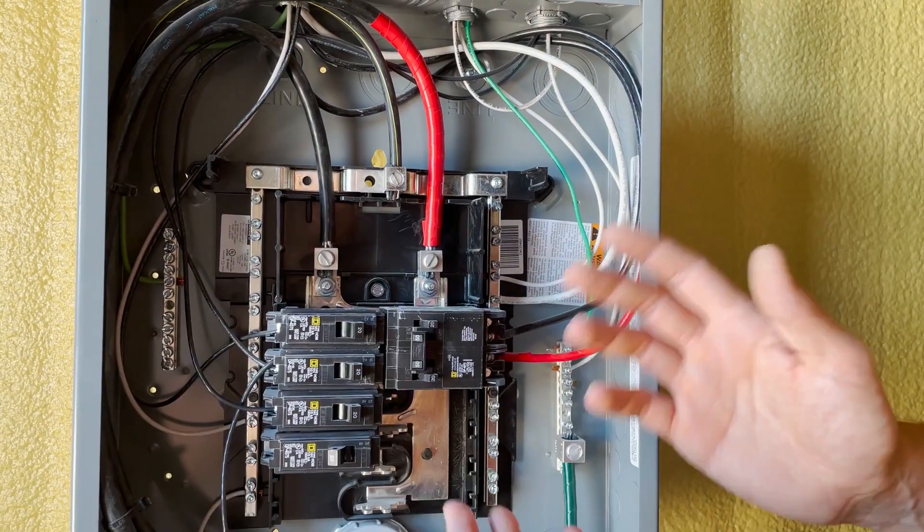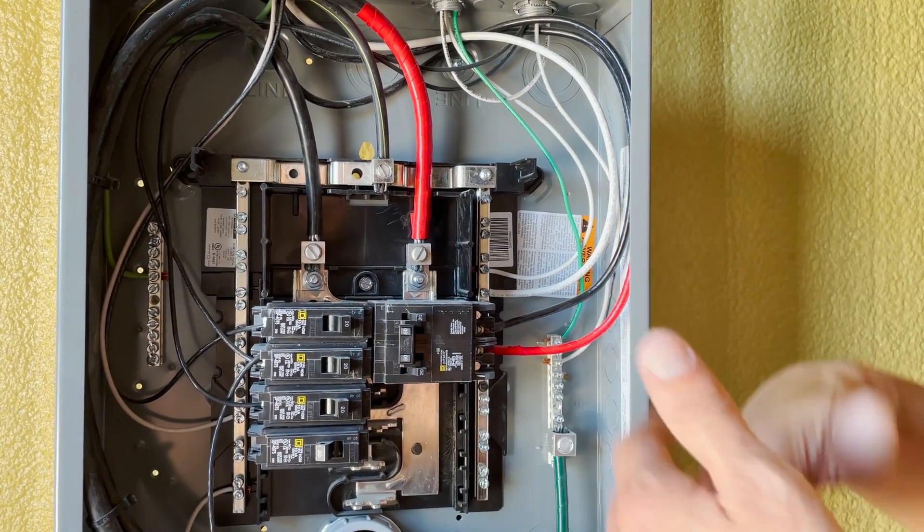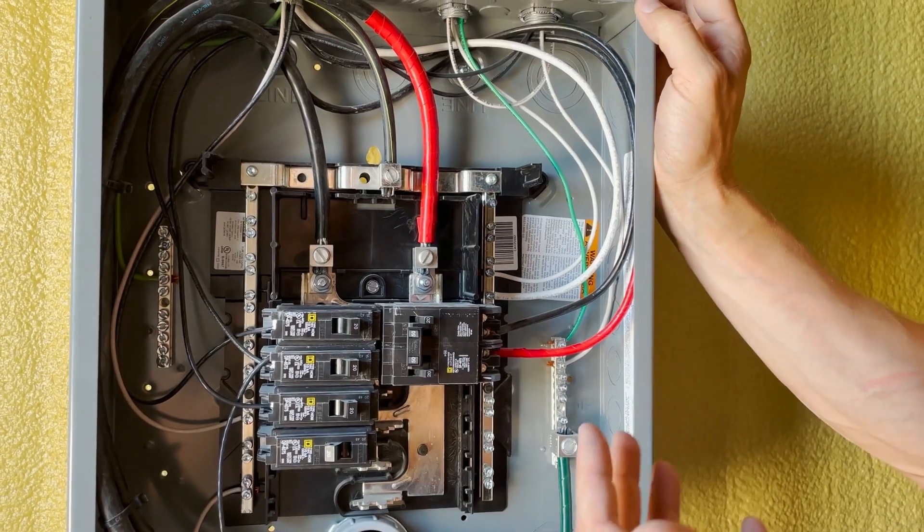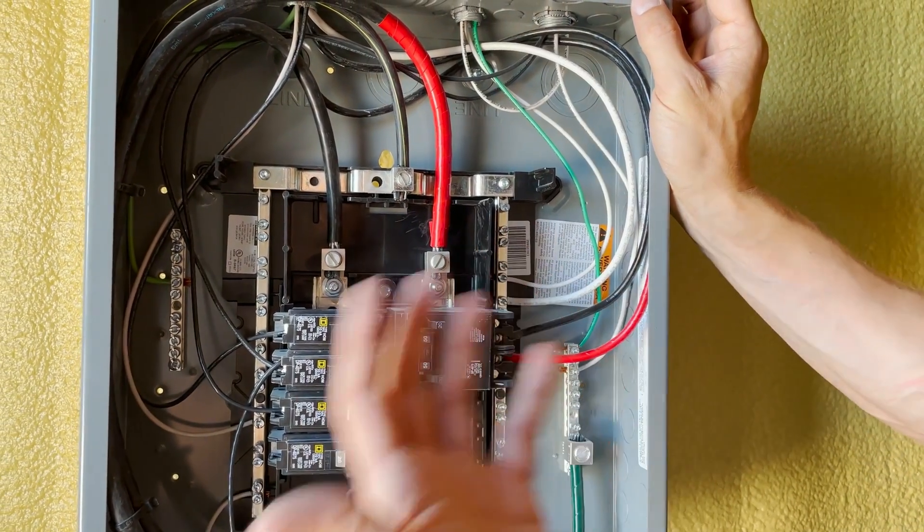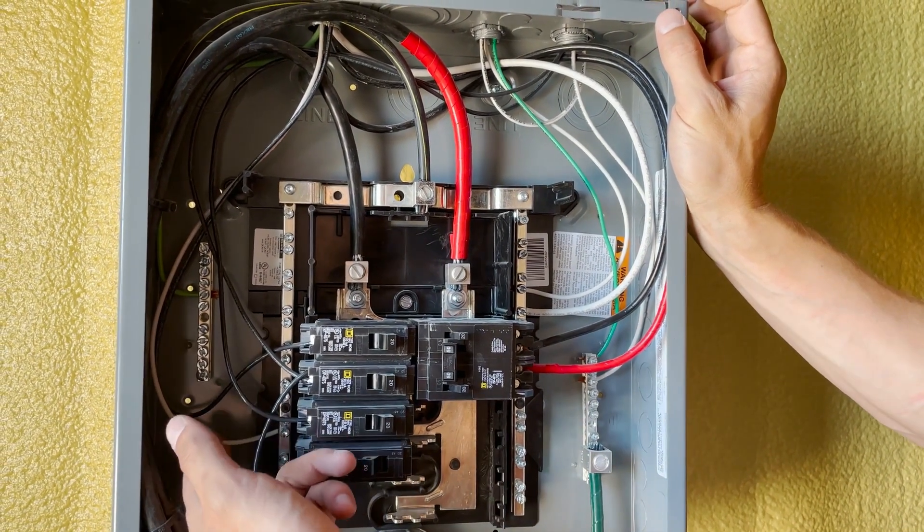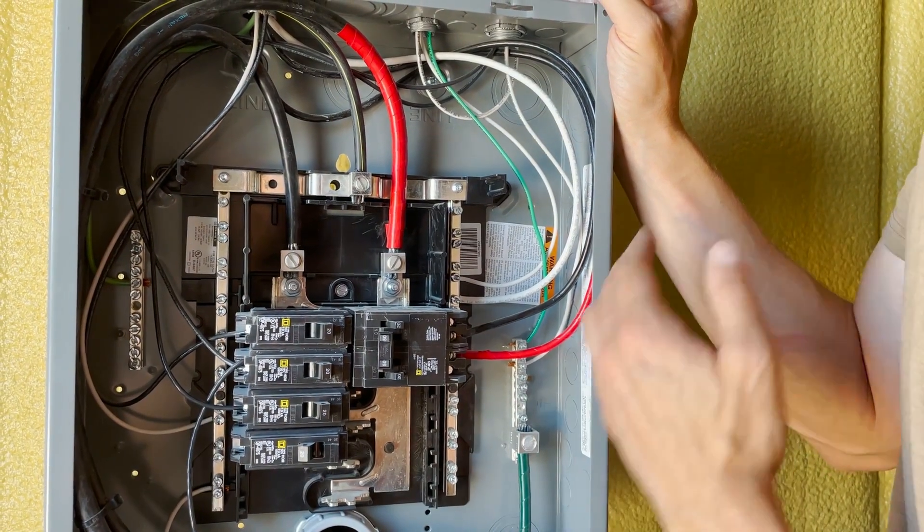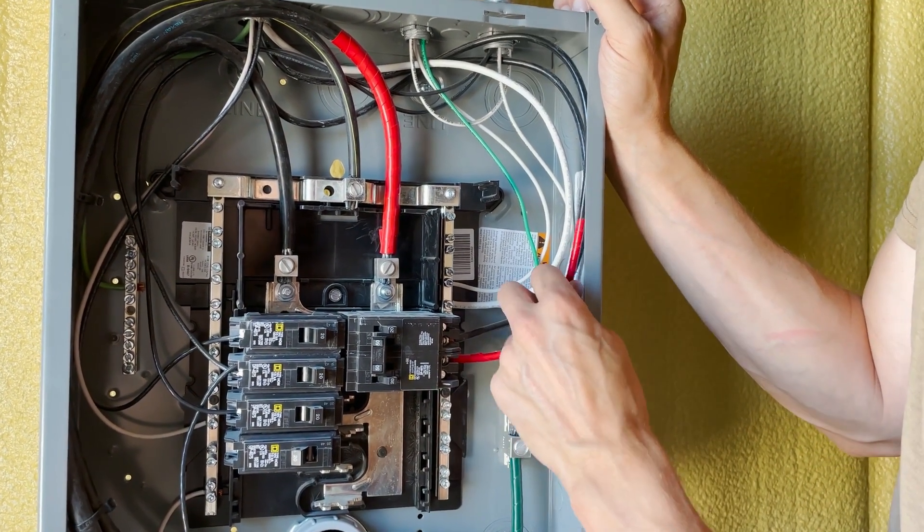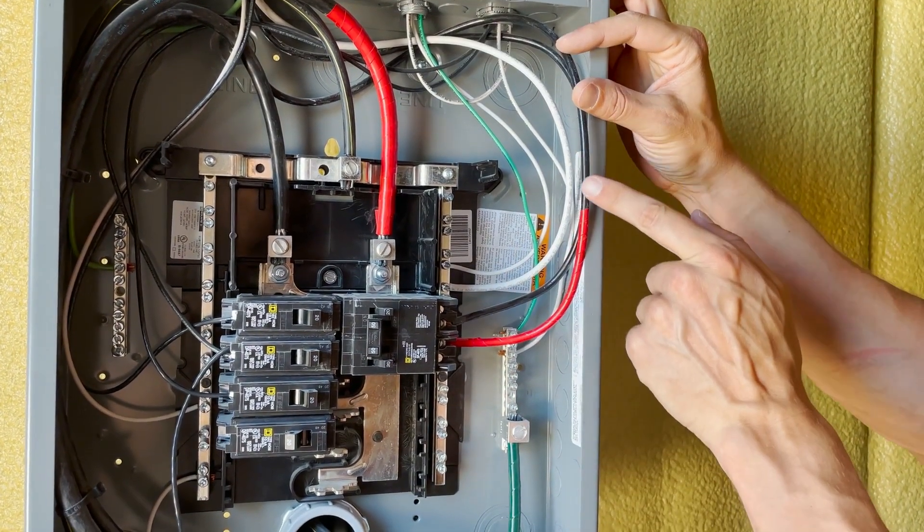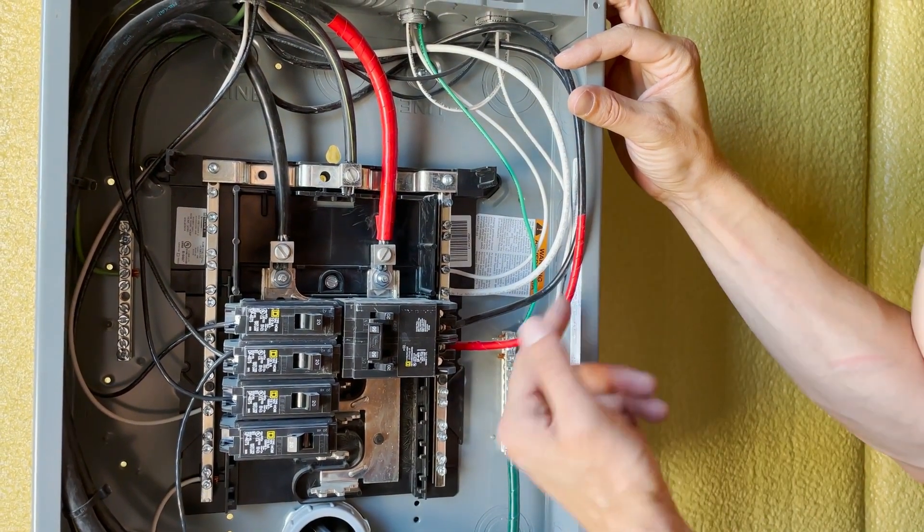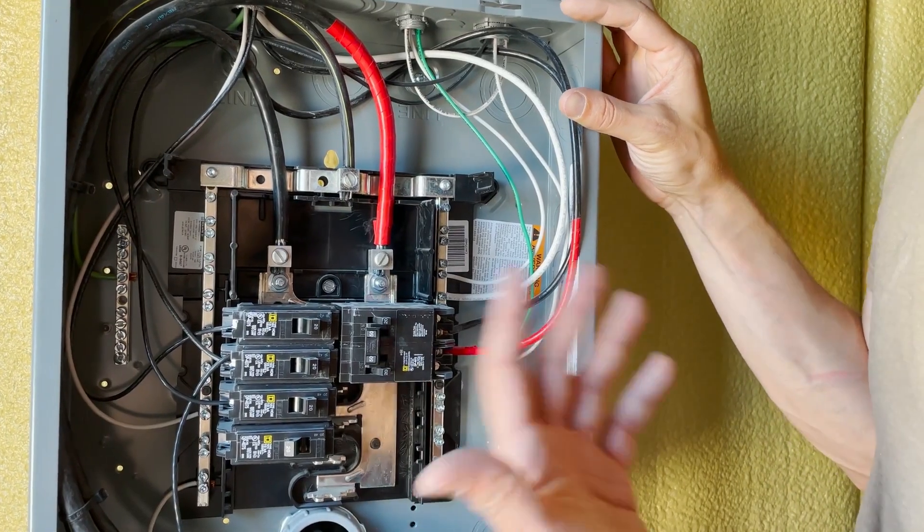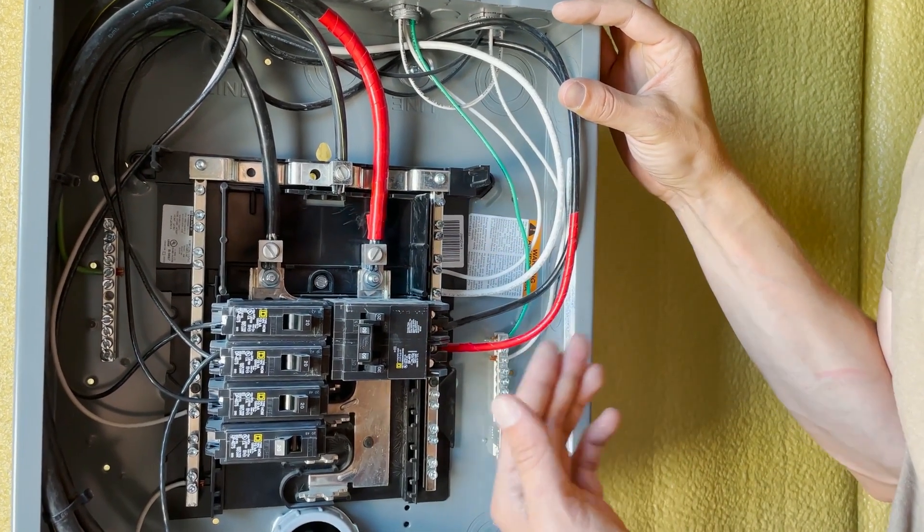Most of the time when you're doing wiring with 12, 10, or 14 gauge—like we discussed in our ampacity video—you only have your two conductors, your black and your white. However, since this is THHN, you just run an extra wire. The electrician that ran this just had a lot of black wire, so instead of running a separate red wire, he took a black wire and wrapped it up with red tape. But if you have the time or ability, you can get a red wire.